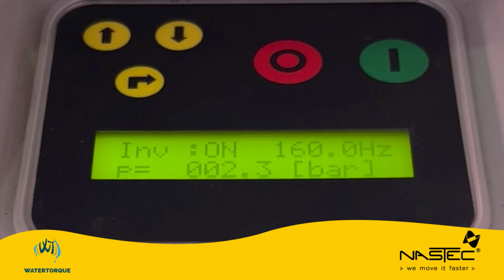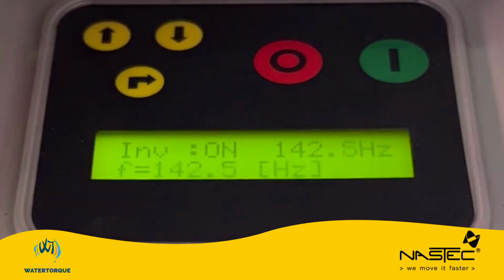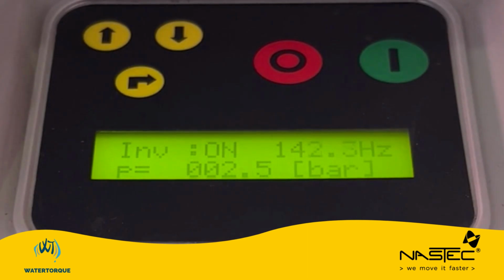What I will do now is gate the valve back on the discharge, and you will notice that hertz will decrease and the pressure will remain pretty steady. So the pump is operating at 2.5 bar. Now what we will do is shut off the valve, which is going to achieve the maximum alarm value, and turn the pump off.